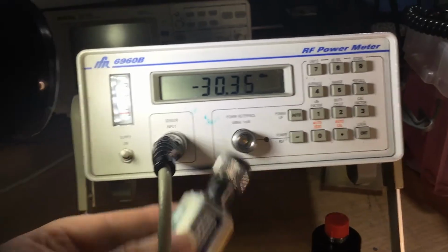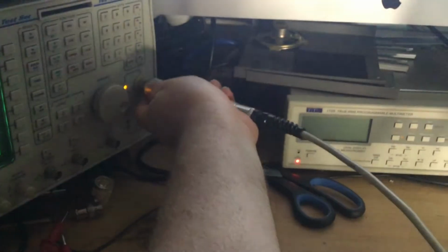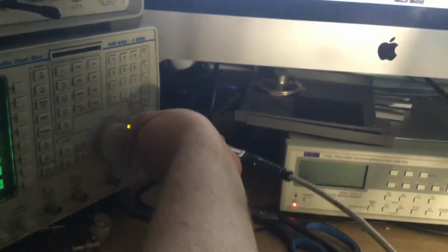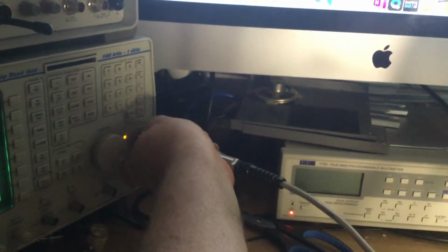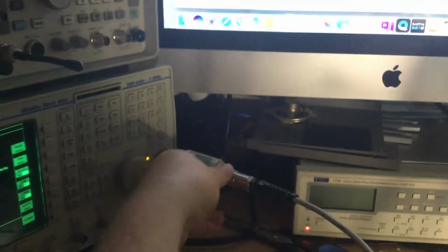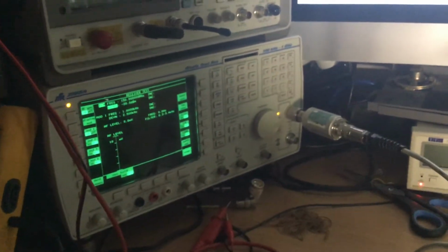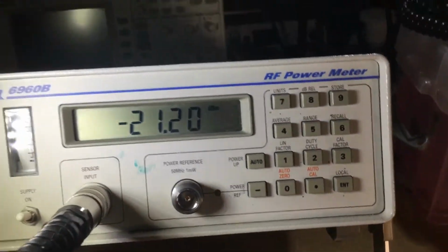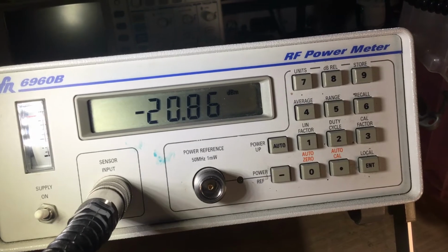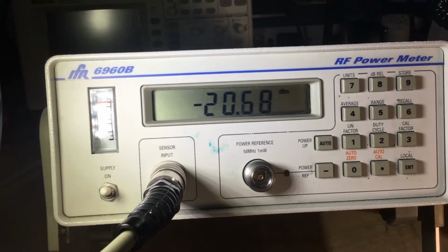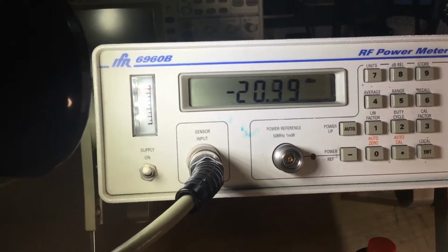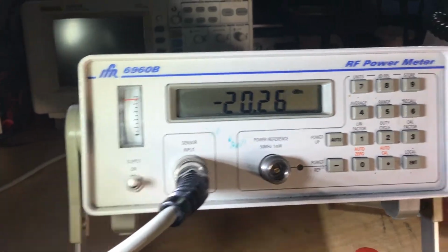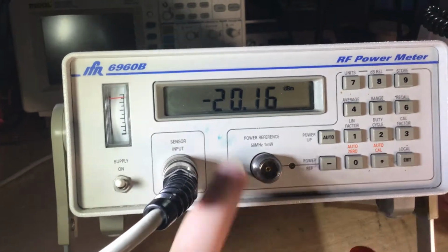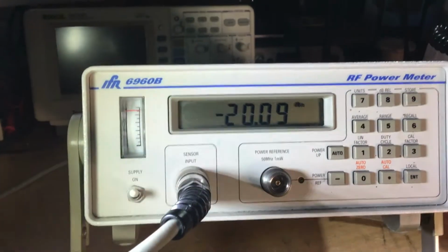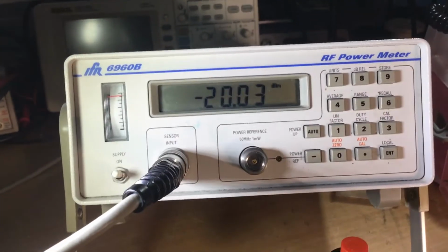We've calibrated the sensor to 0 dBm, and all we need to do is physically connect it onto the N-type connector on the RF signal generator, and make sure it's nice and snug, not over tightened, but just tight enough. And then we've got the measurement coming up now. So this is averaging and settling, and you can change the ranges as well. We've got the little meter just here, which is measuring. So it says minus 20 dBm, which correlates to what we were sending out on the radio test set on the signal generator.